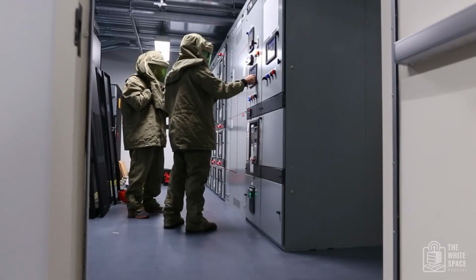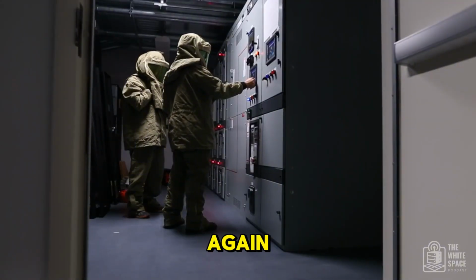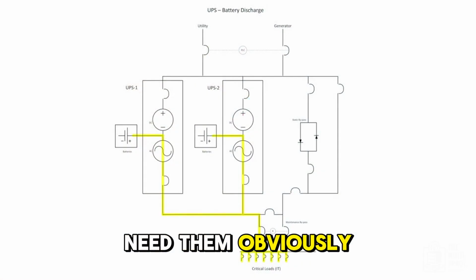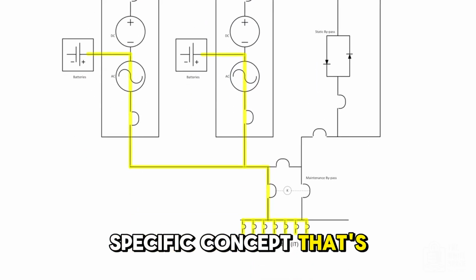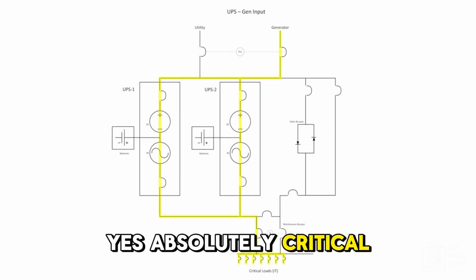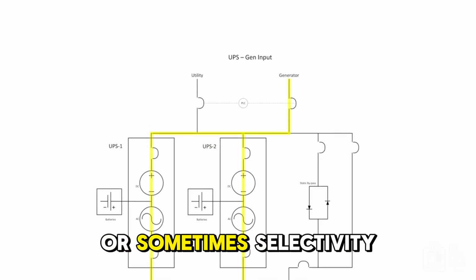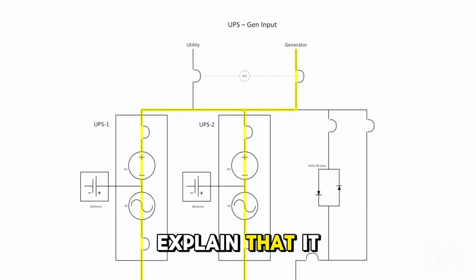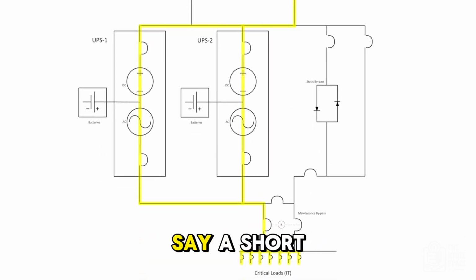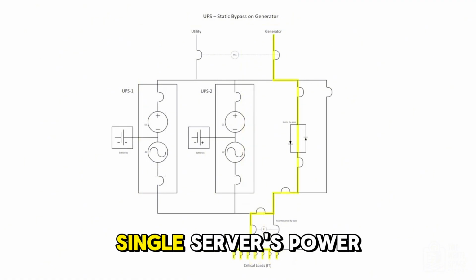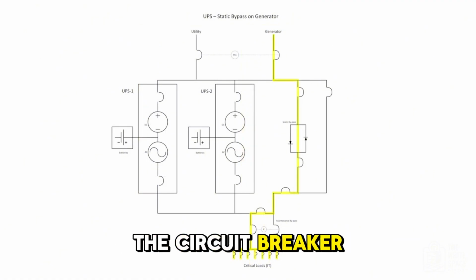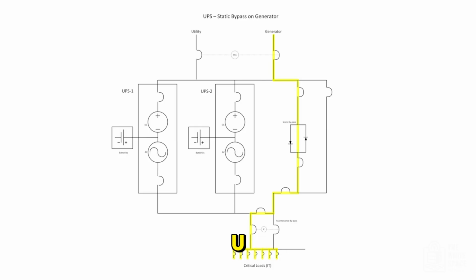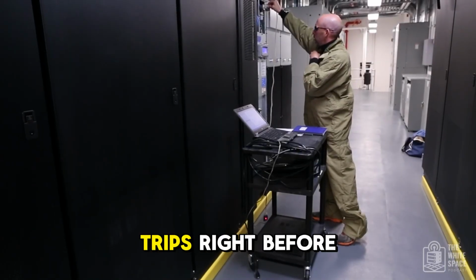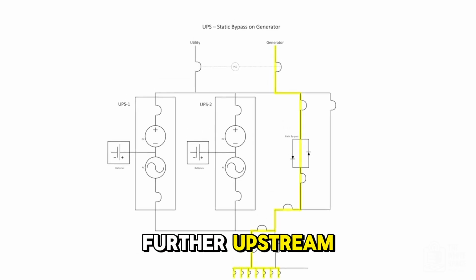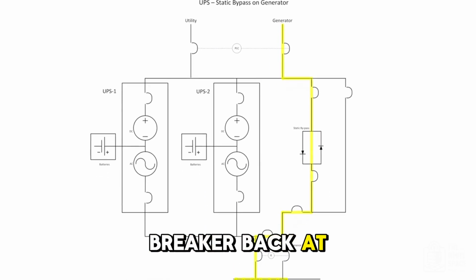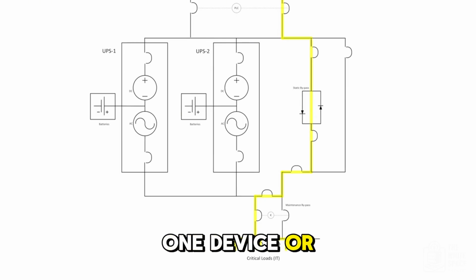Cost and space. Okay, down at the rack level again. Circuit breakers. We need them, obviously, but there's a specific concept that's crucial, right? Yes, absolutely critical. It's called circuit breaker discrimination, or sometimes selectivity. Discrimination. Explain that. It means that if there's a fault, say a short circuit in a single server's power supply, the circuit breaker closest to that fault, usually the one on the RPDU, should trip first. Okay, the local one trips. Right, before any larger breakers further upstream, like the one feeding the whole row or the main breaker back at the panel. So it contains the problem, it's just that one device or that one outlet.